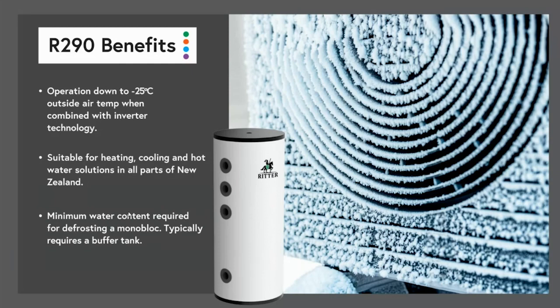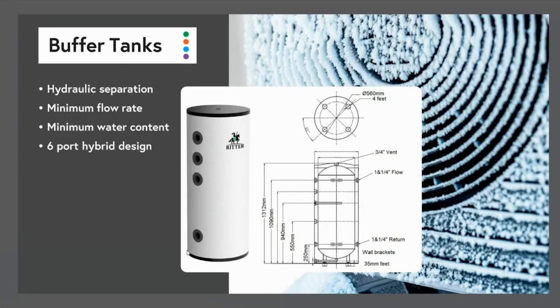However, on any other type of system, like radiators or fan coils, drawing the heat back from those would typically make those systems go cold, and that would reduce the comfort in the house. So what we put in place in the middle of these systems is a buffer tank. The buffer tank means that the water required for the defrosting cycle is stored in the buffer tank, and that energy can be transferred to the heat pump at any time, and it's not going to affect the downstream heating system. So buffer tanks are generally recommended for most systems when using a heat pump.